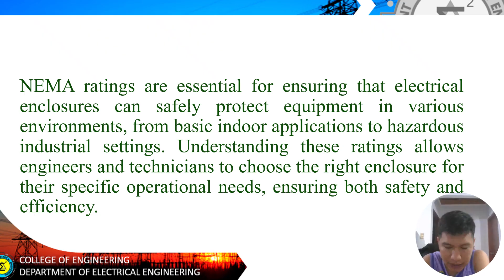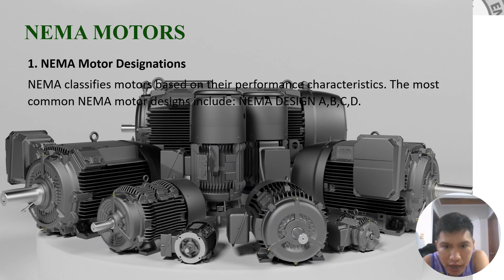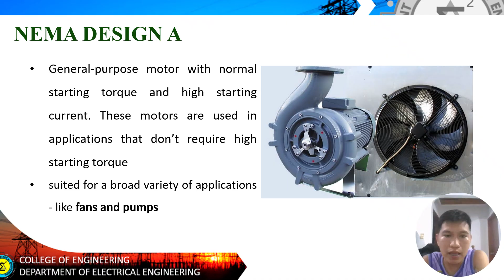Motors and generators also have NEMA designations. NEMA classifies motors based on their performance characteristics. The most common NEMA motor designs include NEMA Design A, B, C, and D. NEMA Design A is a general purpose motor with normal starting torque and high starting current, used in applications that don't require high starting torque, suited for a broad variety of applications like fans and pumps.